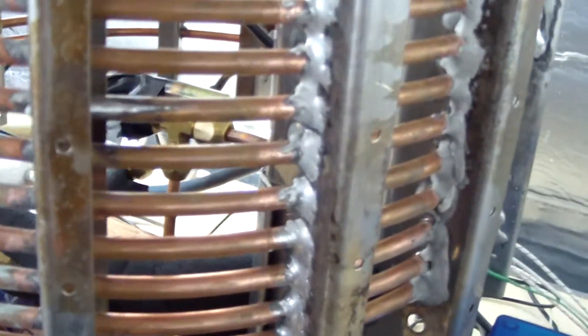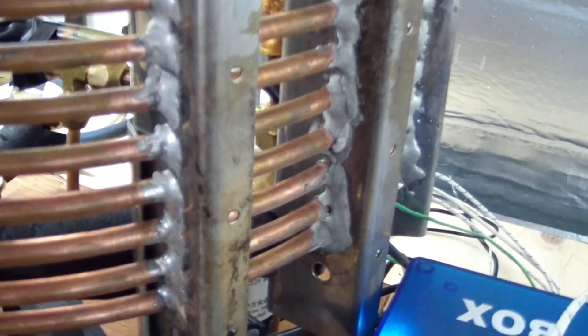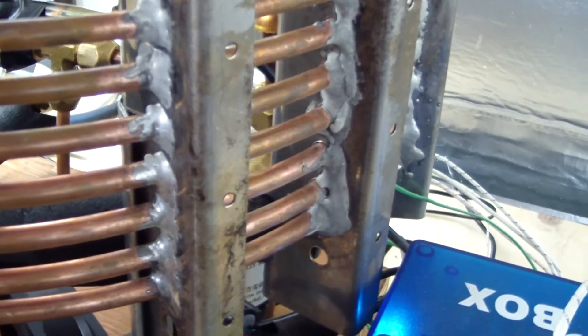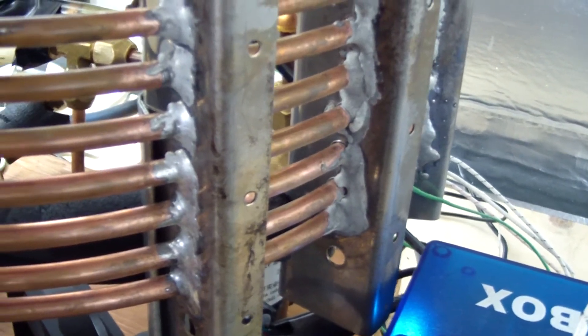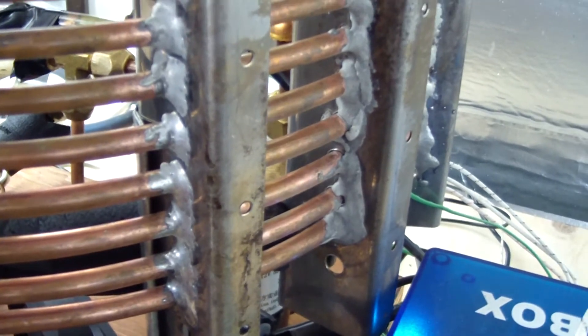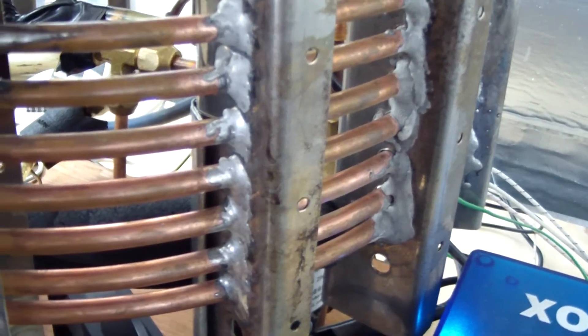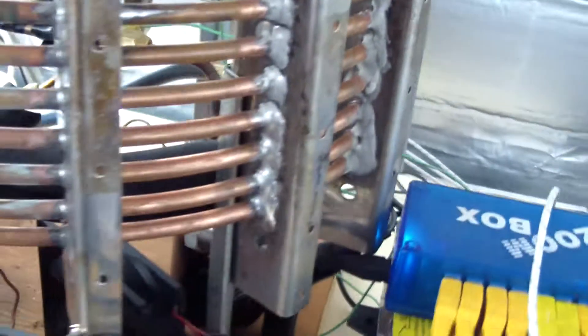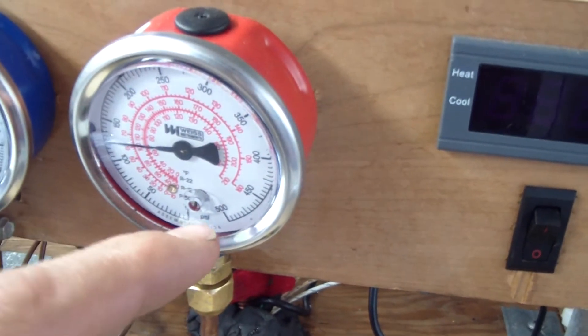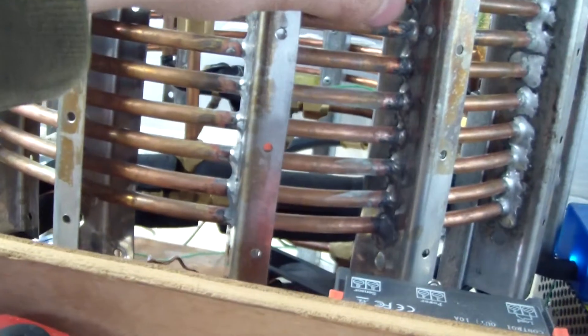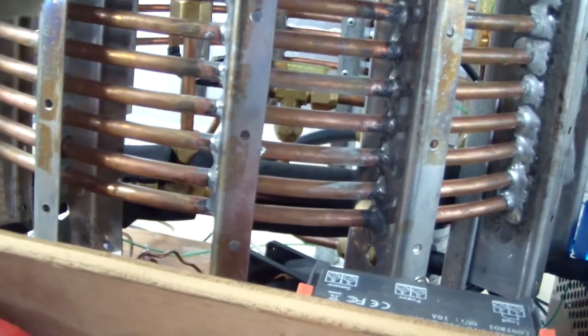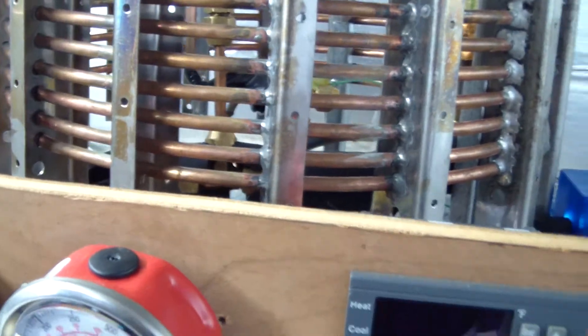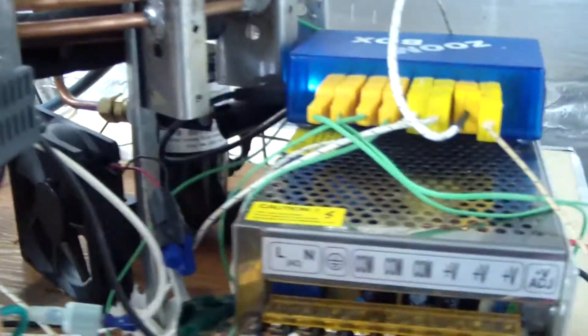Now the reason I mention this is I have concerns, if it does have some kind of a check valve or something that should be shut, that maybe during the actual run, it's leaking back through. So, as the compressor discharges high pressure gas into the condenser, it's leaking back through, leading to inefficient compression.